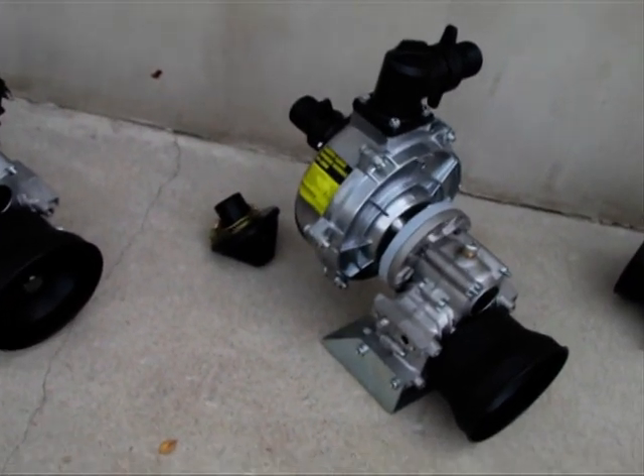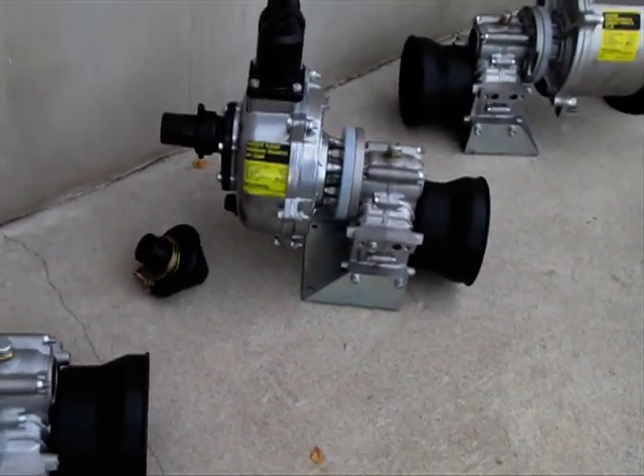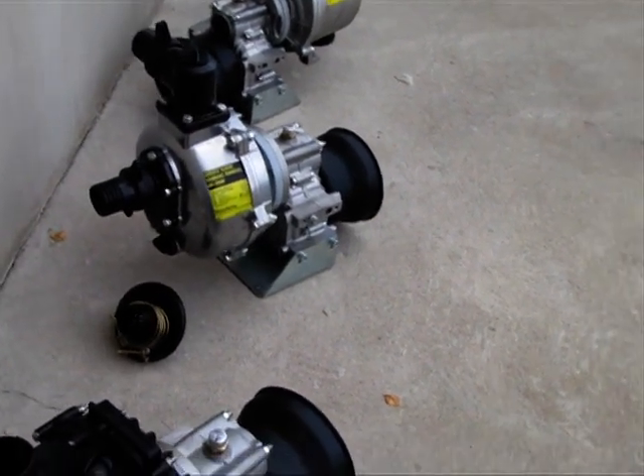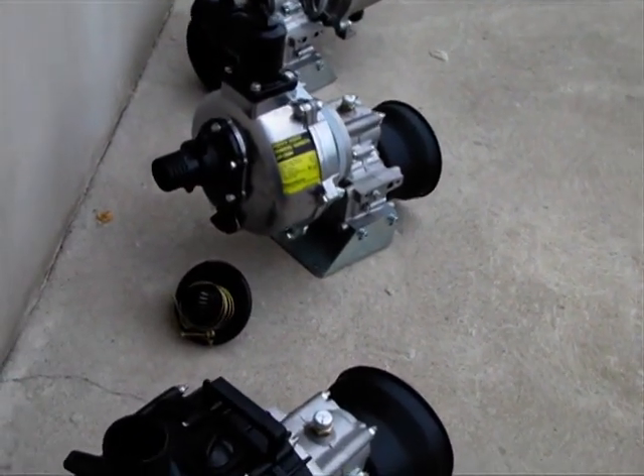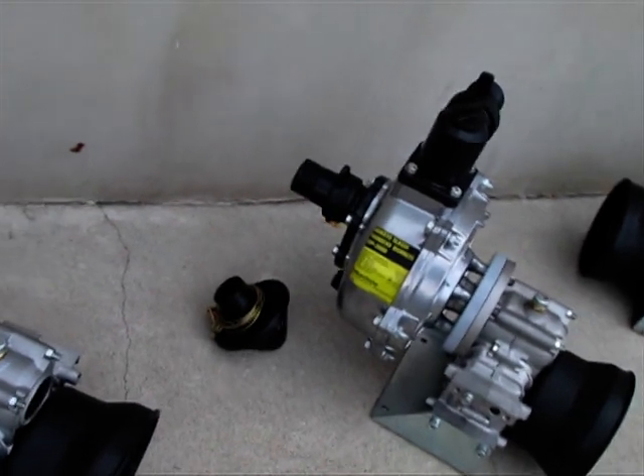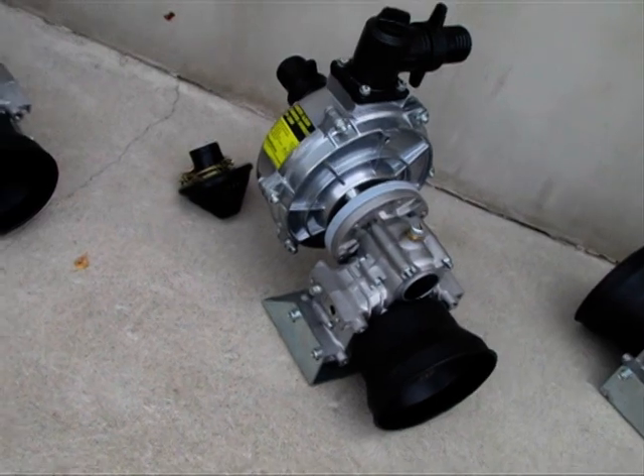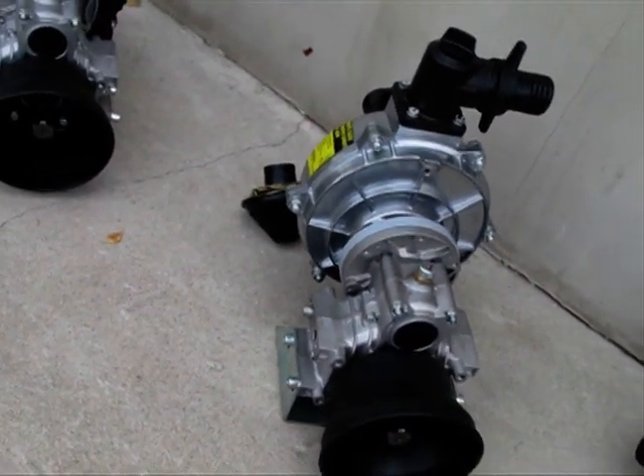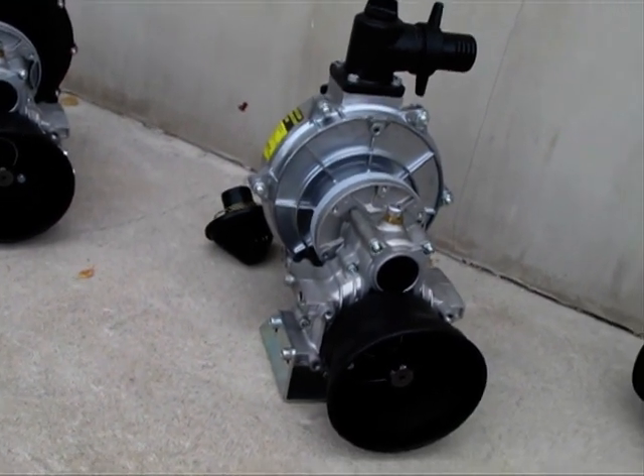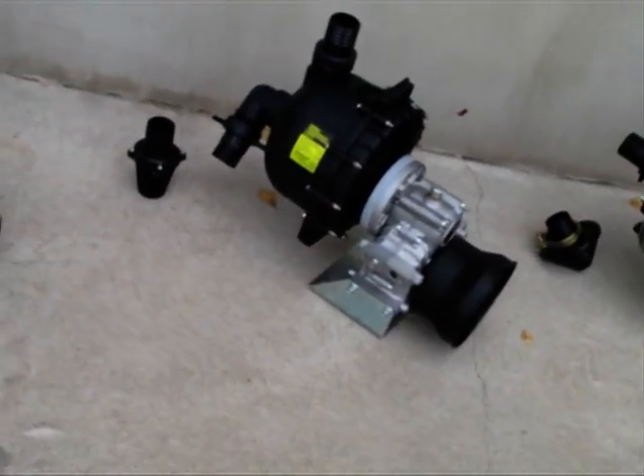The high pressure pump is used for different purposes: filling the water tanks and sprayers, or being mounted on sprayers themselves. It's also used for fire extinguishing and washing machinery. It has 2 inch hose fittings, a capacity of up to 600 liters per minute, self-primes from 7 meters deep, and lifts up to 60 meters high.